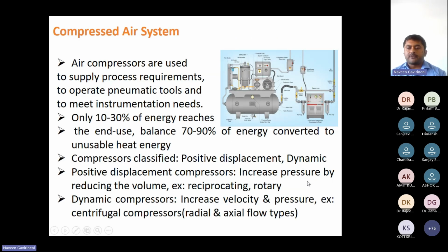After the boiler, one of the most important topics is the compressed air system. With the compressed air system, the pneumatic valves and the valve or damper arrangements will operate on pneumatic air. In the olden days, people used a hydraulic system, but the hydraulic system is very costly, needs so much maintenance, and there is oil leakage also. For that purpose, after a lot of study, this came.